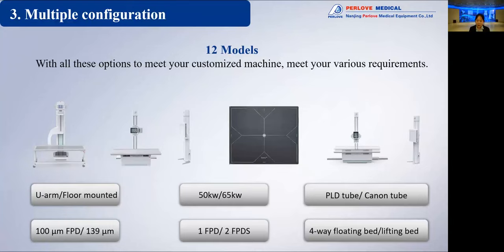For the flat panel detector, we have two sets for choices to install in the floor-mounted X-ray. Why? Because for the floor-mounted X-ray, we use the flat panel detector both in bed and back stand. With two flat panel detectors, we don't need to remove them from one side to another, reducing the possibility of damage. For the floor-mounted X-ray, we also have two bay types, like the floating bed and lifting bed. All of these configurations benefit you to meet different requirements from hospitals.